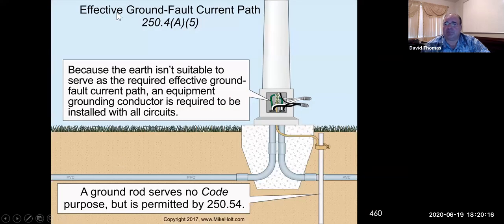And then because the earth isn't suitable to serve as a required effective ground path, we still have to run a ground in our conduits. Now, sometimes we will do these ground rods by these poles.